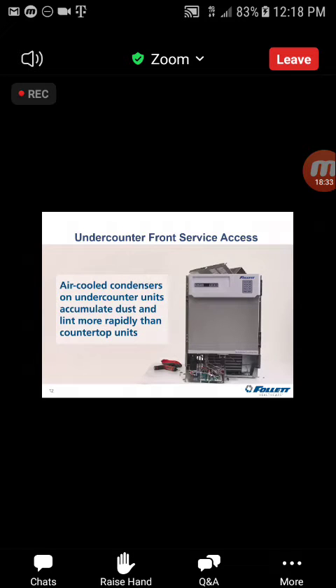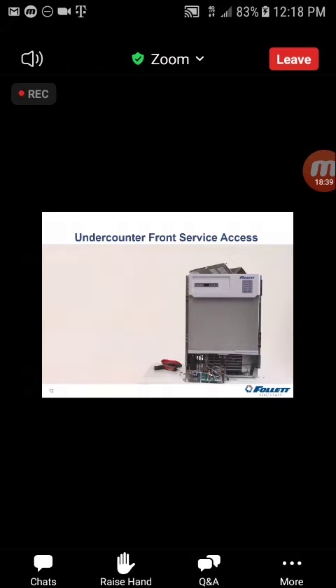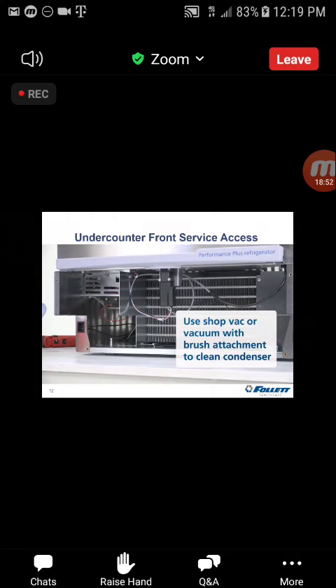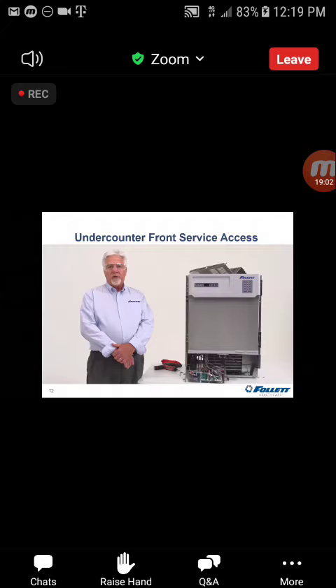It's important to remember that air-cooled condensers on under-counter units tend to accumulate dust and lint more rapidly than units located on a countertop. Air filters should never be installed in front of condensers on any Follett refrigerator or freezer. The condenser fan motors are not designed for this. A shop vac or a vacuum can be used with a brush attachment to remove any dirt or lint from the condenser. Follett recommends deep cleaning the condenser with compressed air every few years.